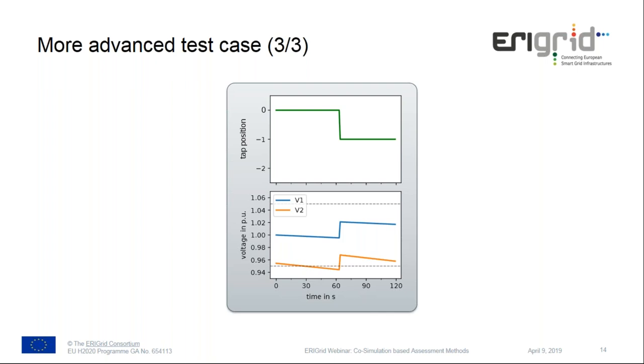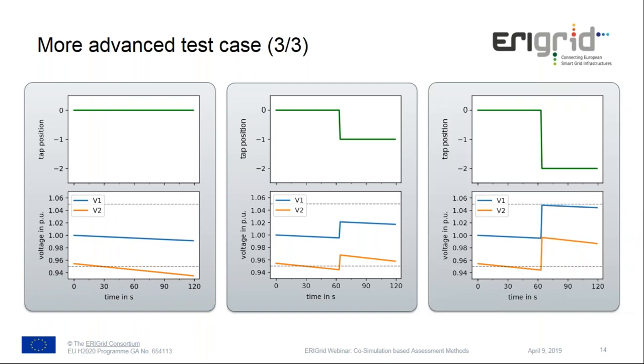If you indeed implemented using the communication simulation and so on, what you realize is that things do not always happen as you would expect them, meaning that under certain circumstances, due to dead times of the controller, due to communication delays and so on, there's quite some complexity even in this simple test case, you can end up with results that you didn't expect, like nothing happens, or actually the tap position may change by 2 taps at once.